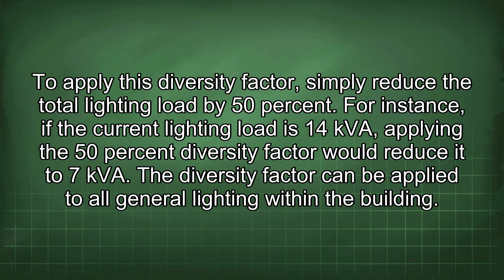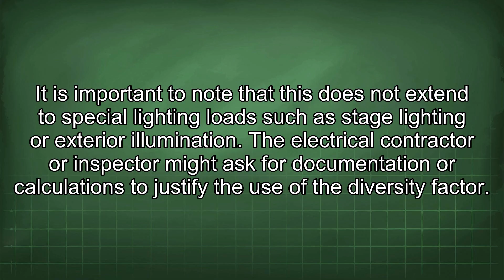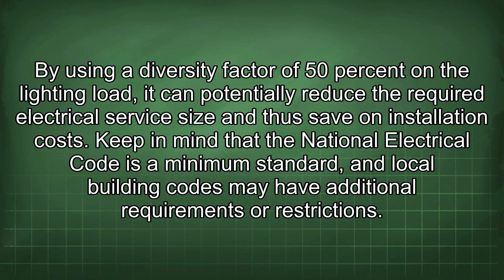It is important to note that this does not extend to special lighting loads such as stage lighting or exterior illumination. The electrical contractor or inspector might ask for documentation or calculations to justify the use of the diversity factor. By using a diversity factor of 50% on the lighting load, it can potentially reduce the required electrical service size and thus save on installation costs. Keep in mind that the National Electrical Code is a minimum standard, and local building codes may have additional requirements or restrictions. Always consult with a local building inspector or a qualified electrician for specific guidance.